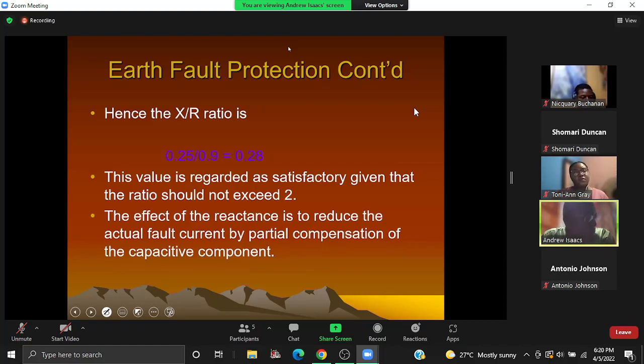Now, in terms of transformers, when we talk about transformers, we have only specified the per unit or the percentage rating. But in many instances, you will get the X to R ratio of the transformers. It's in most data sheets that you get that information.